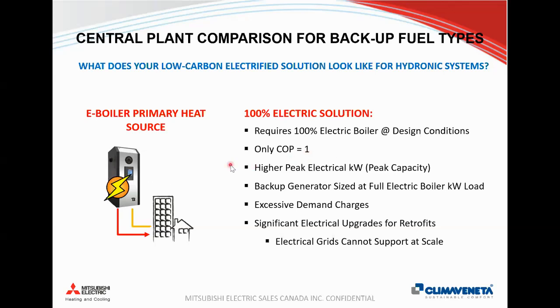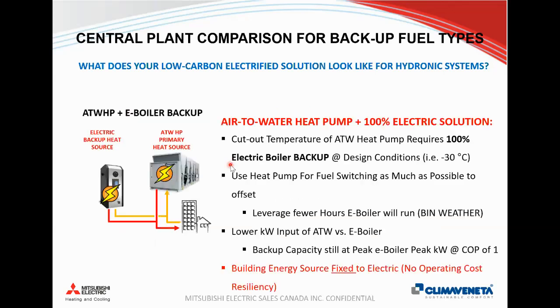But ultimately, I think we can't just change every gas boiler to an electric boiler and call it a day. We've achieved net zero. A lot of buildings don't have power to support shifting all the BTUs to electric, and it can't be done at scale, really. With the amount of electric cars that we have to put onto the grid, plus decarbonizing and electrifying a lot of buildings, there's just simply not enough distribution or enough power to actually just do this at a COP of 1. So we do need the heat pump to leverage the COP from the heat pump.